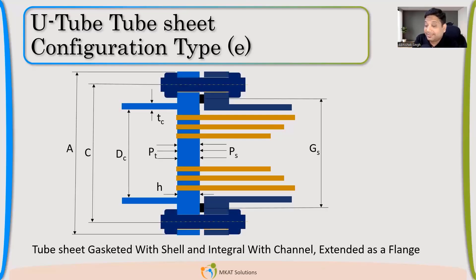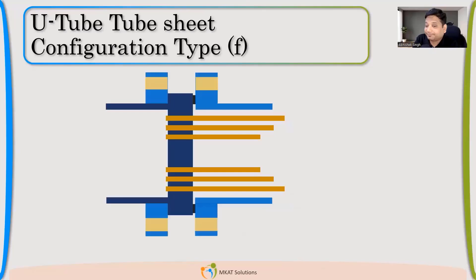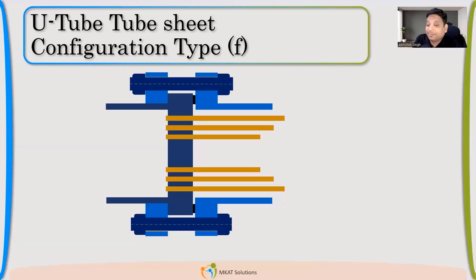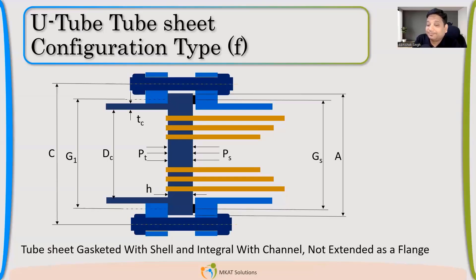Now E type — going in the opposite direction. The tube sheet is integral with the channel. This may be a one-pass configuration with no partition plate, but we are studying the configuration. So integral with channel — if I say tube sheet integral with channel, you should be able to draw this configuration knowing that integral means welded. This is Type E. Now F is opposite to E, where the tube sheet is integral with the channel but there is a lap-type flange, so it will be bolted. This is F type.